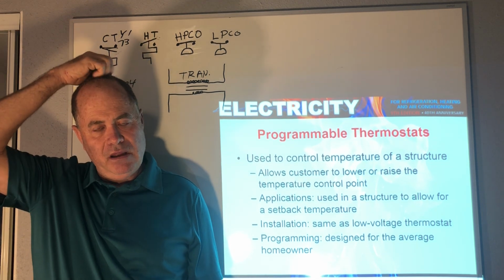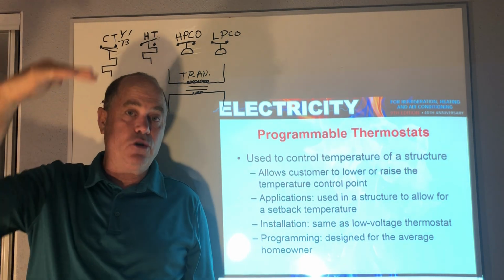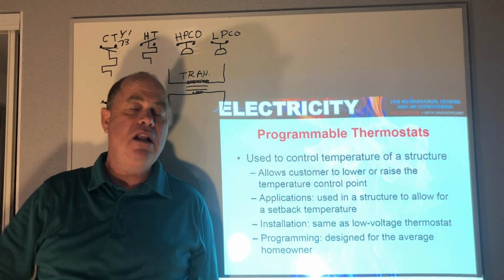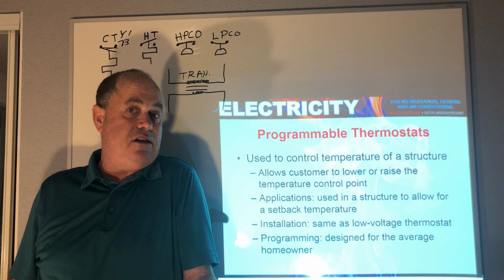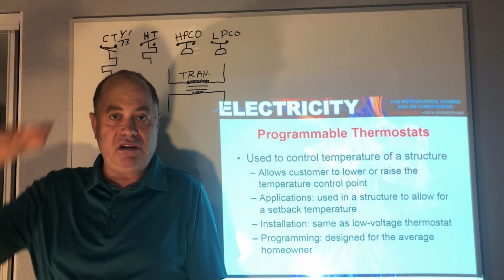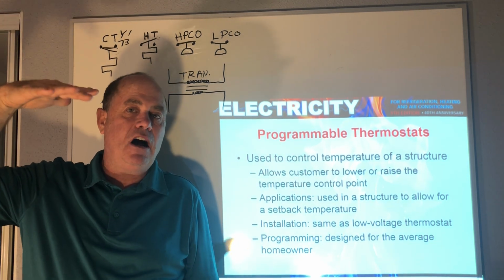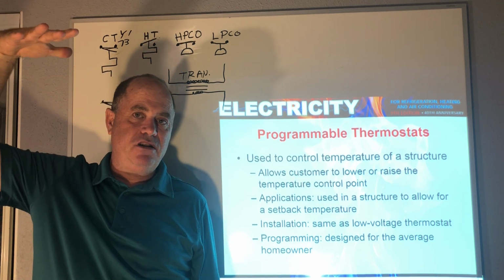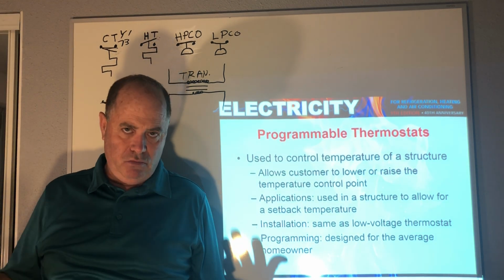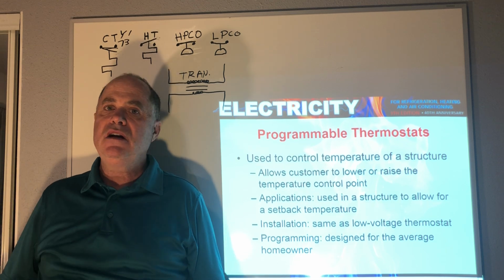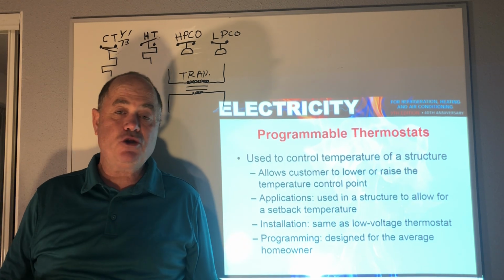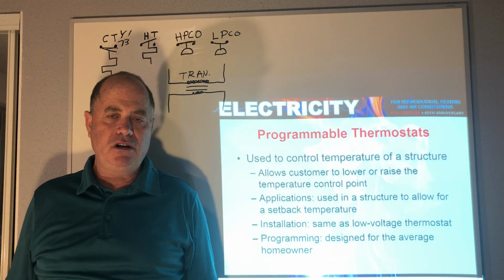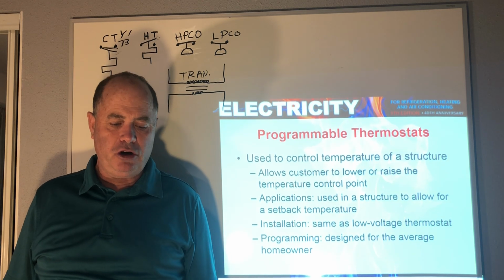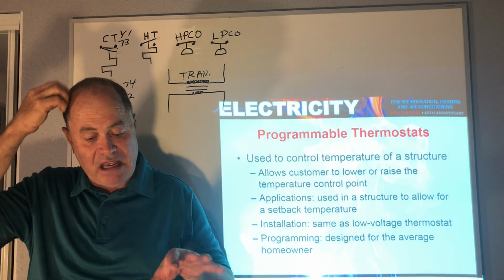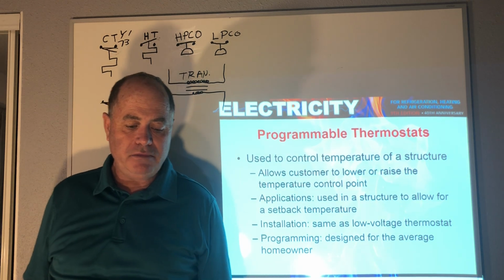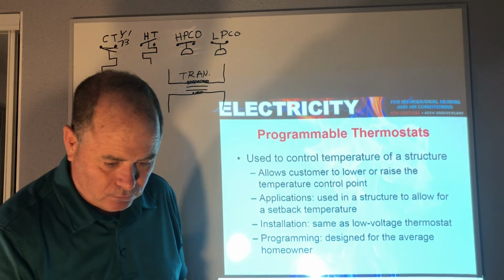So they do that setback where when nobody's there, they'll cool down to like 82 or 84, and when nobody's there, they'll heat up to like 56 or 57 degrees. And in a sense, the system is off, but if you had radical temperatures in the building, also, when buildings aren't occupied, they're being cleaned, repairs are being made, so it keeps it somewhat comfortable for the workers. Okay, so that concept of setback is important to understand.